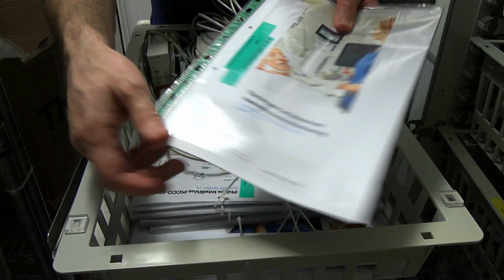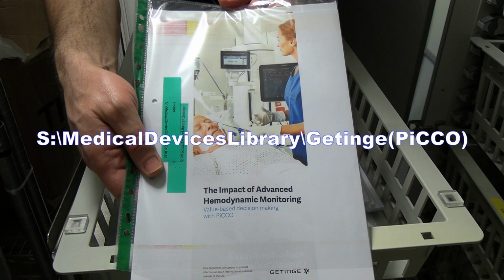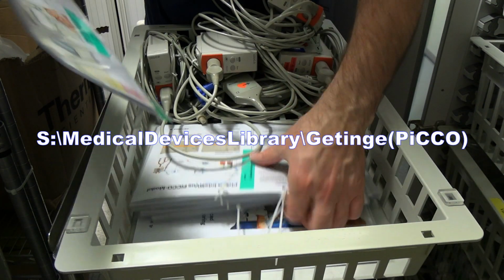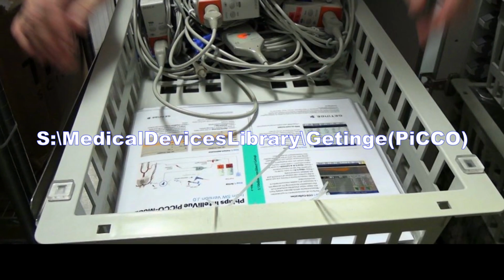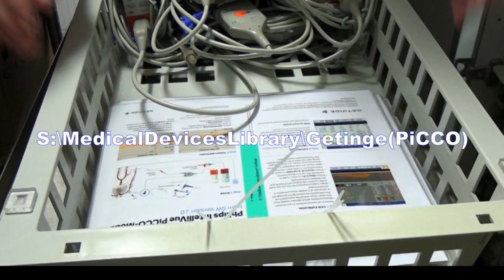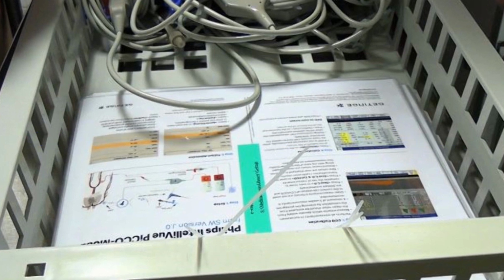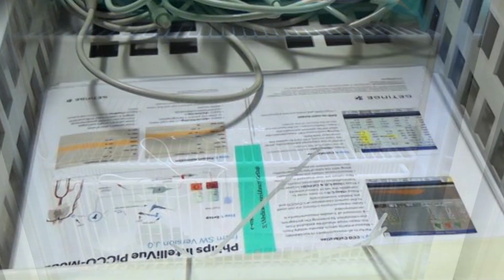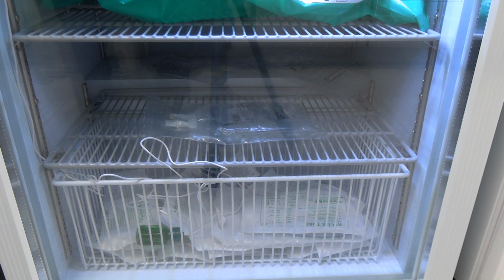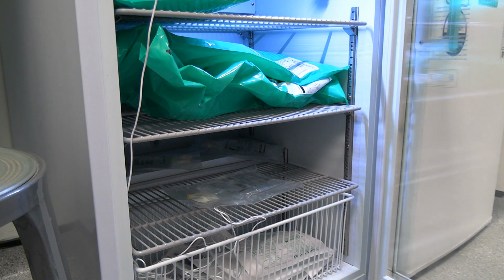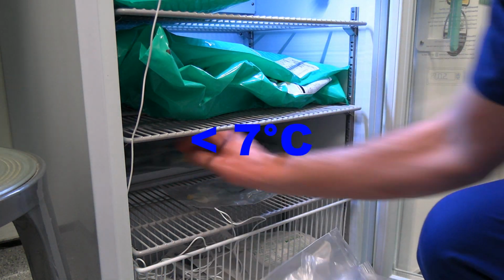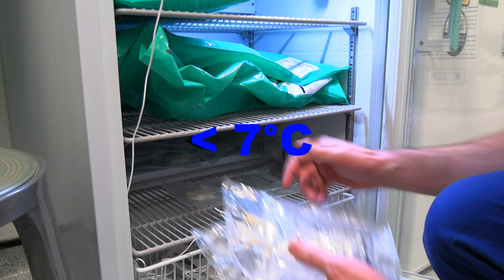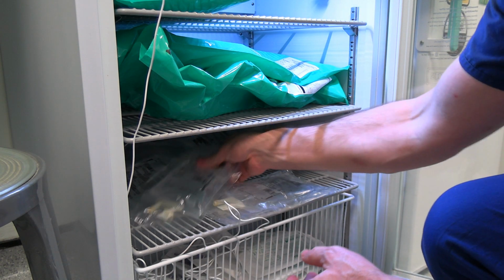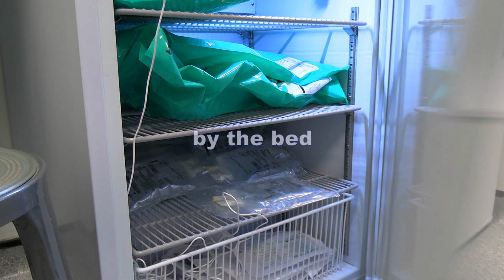All these documents are available on the S drive at Medical Device Library /Getinge, PiCCO. Also, kindly ensure that you have access to the S drive. If not, please contact the IT department for assistance. Once PiCCO plans are initiated, please ensure to check the fridge for 250 ml bags of normal saline. You will need 6 bags per day, and they require a few hours to cool to below 7 degrees Celsius. We opt for 250 ml bags because they are less susceptible to temperature fluctuations over short periods of time.